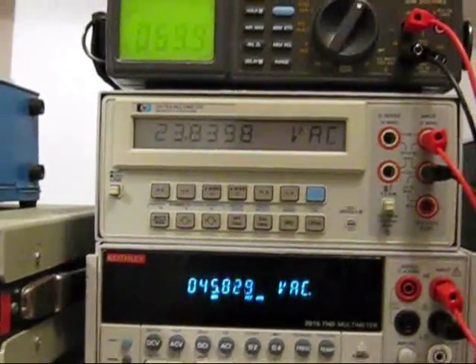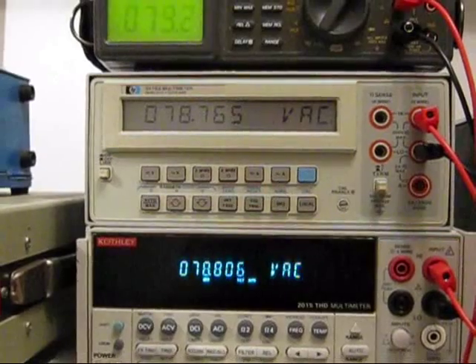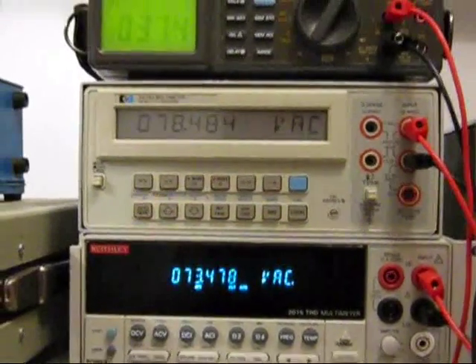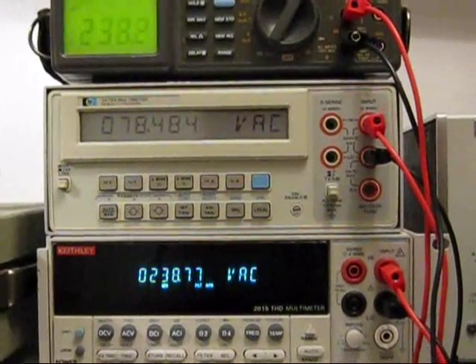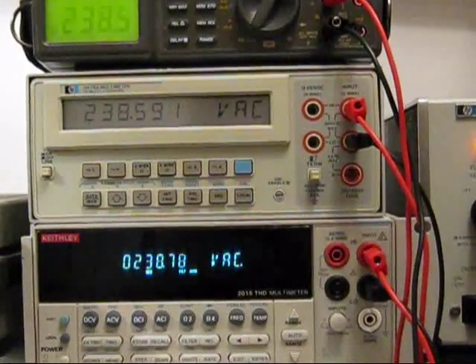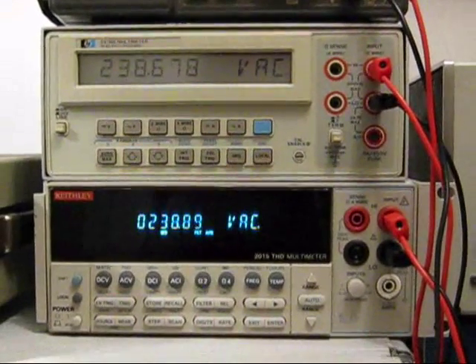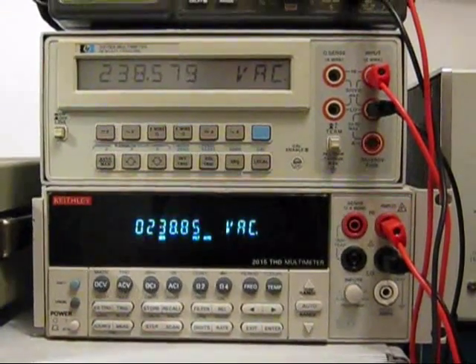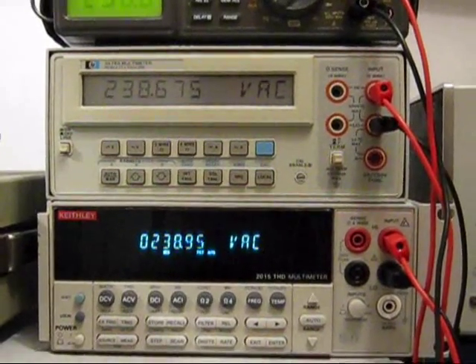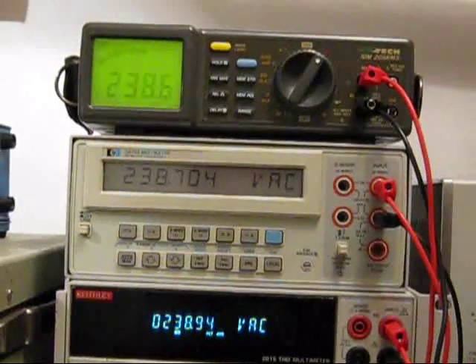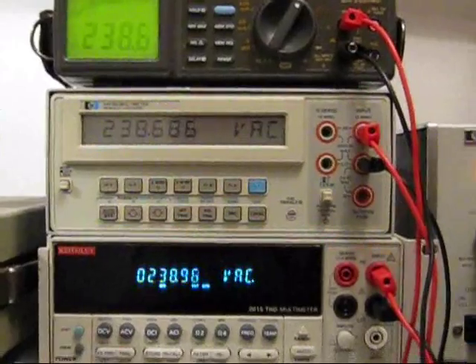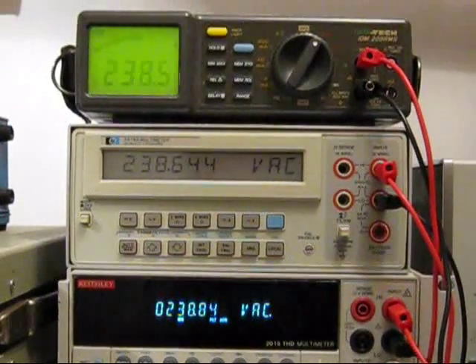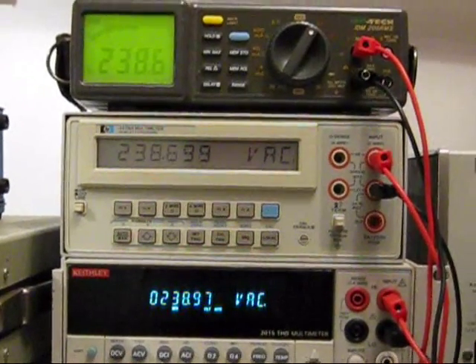I think they're all showing 23.8. And what we're going to do, we're going to go up a range. And when we reset the calibrator, we'll now see that we've got 238.9 volts on the Keithley, 238.6 on the HP, and 238.5 on the Isotec.